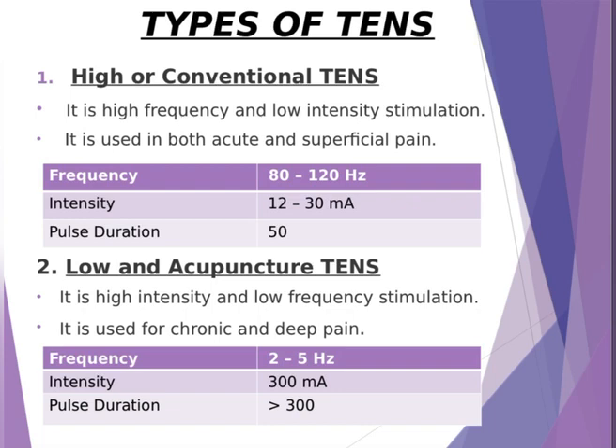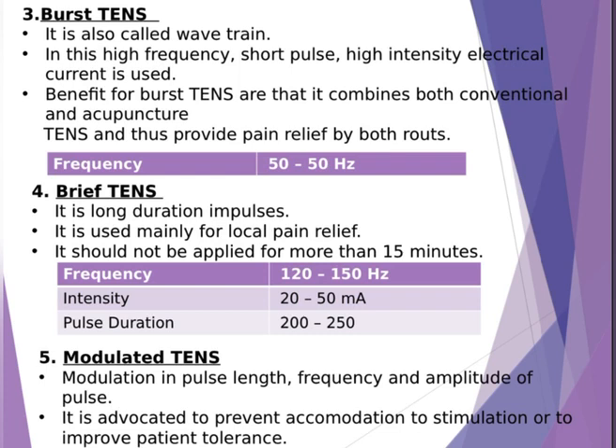There are five types of TENS. Number one: high or conventional TENS. It is a high frequency and low intensity stimulation. It is used in both acute and superficial pain. Number two: low and acupuncture TENS. It is a high intensity and low frequency stimulation. It is used for chronic and deep pain. Number three: burst TENS, also called wave train. In this, high frequency, short pulse, high intensity electrical current is used. The benefit of burst TENS is that it combines both conventional and acupuncture TENS and thus provides pain relief by both routes.